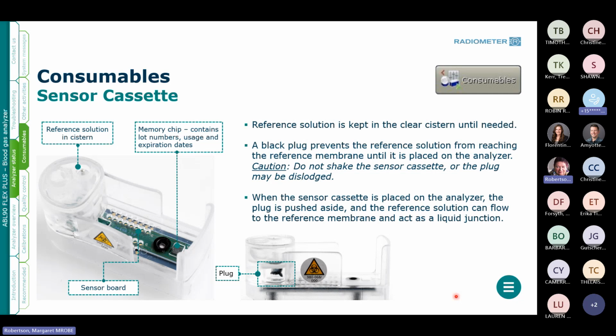And the same thing with our sensor cassette. So that's the other consumable. Again, the top part of the sensor cassette has reference solution. When it's in its little container, before you take it out and put it in the analyzer, this reference solution won't spill out. Once it's been activated, and what that activation does is when you put it on the analyzer, it opens up the little plug so the reference solution can flow easily out of it. So when you take the sensor cassette out, you want to make sure that you don't tip it or turn it upside down. Otherwise, you could leak some of that reference solution out. So you just pick it up, and the video that we went through shows you how to pull that sensor cassette out.